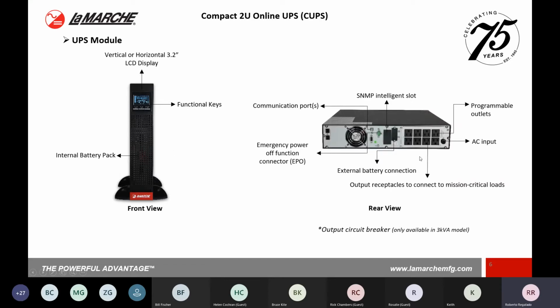So now with the module on a horizontal axis, you can see the back of the module. You can see where you have your AC input connections, your output programmable outlets, your external battery pack, which is typically the SB style connector. I'm not exactly sure on the specific number of the SB connector. And you do have an EPO functionality button here that you can wire out if you have that on your system.